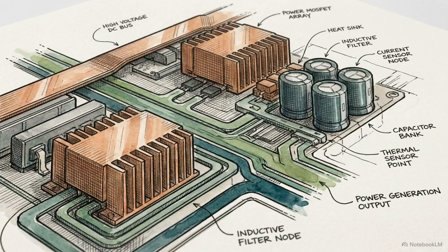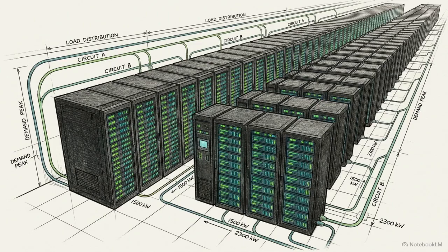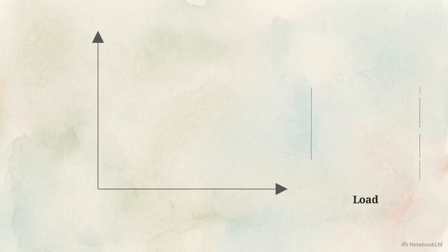Next, differentiate between the inverter and the output. Inverter output confirms what the power electronics are internally generating. UPS output shows what the physical load is actually demanding. Look at this power triangle to understand the load demand on the output screen.